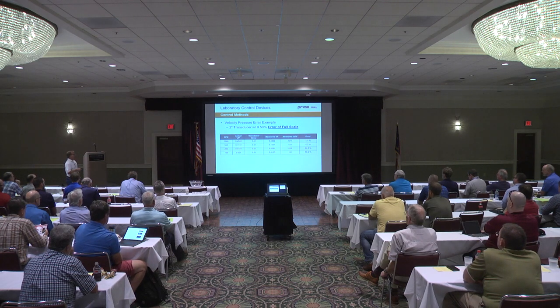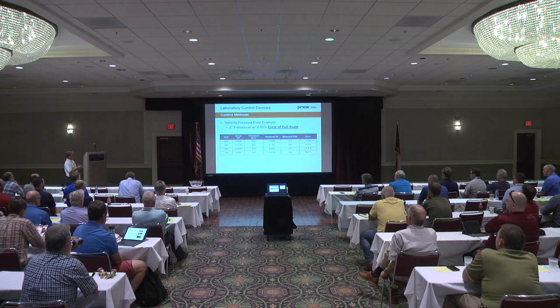So here's an example of errors in full scale in your velocity pressure reading devices. Obviously the higher pressure or the higher flow range is going to generate a lower error because you have enough velocity pressure to give you a better reading. But as you lower the CFM, your errors start to compound because of the errors in the devices and the transducer and lower velocity pressures.